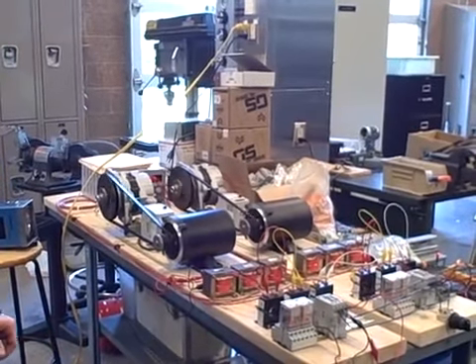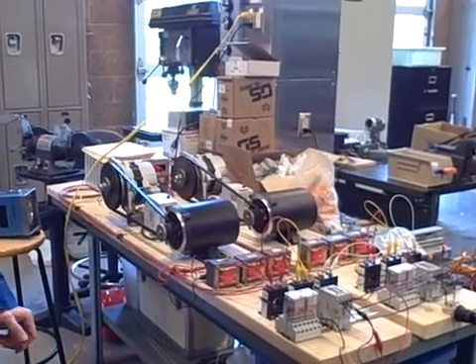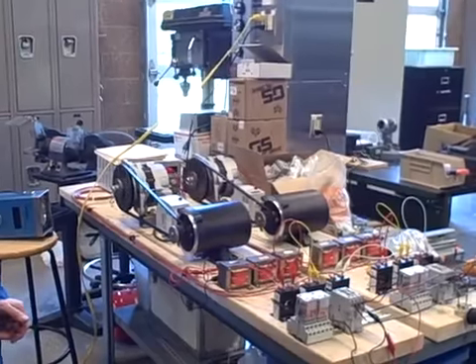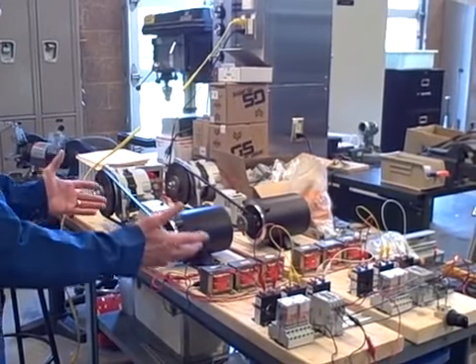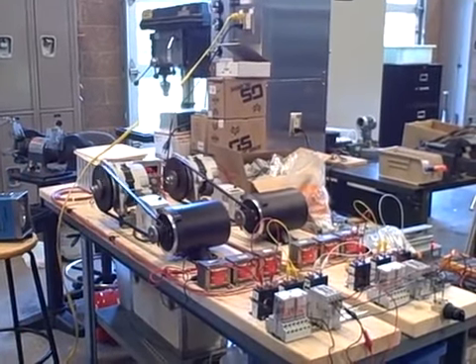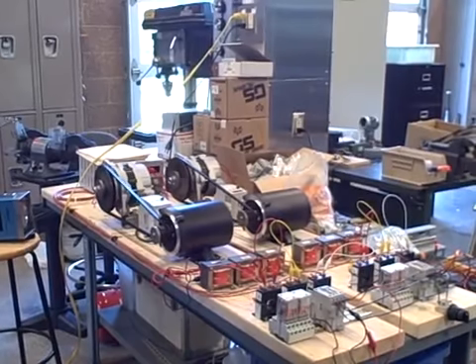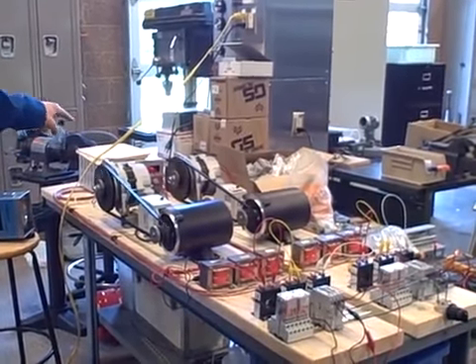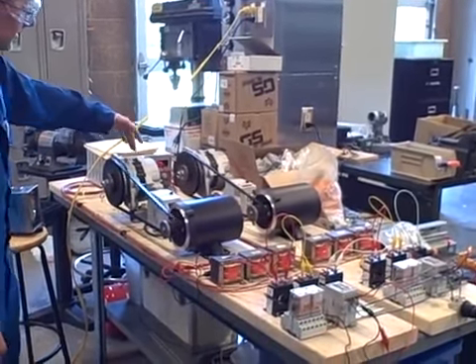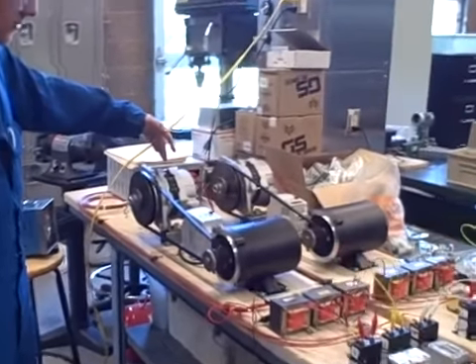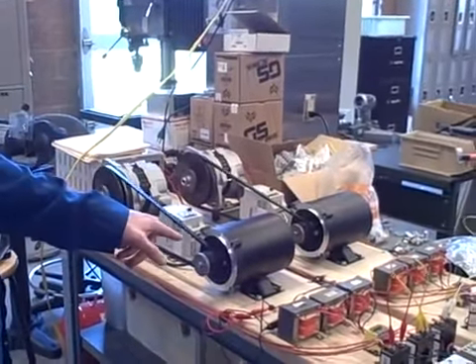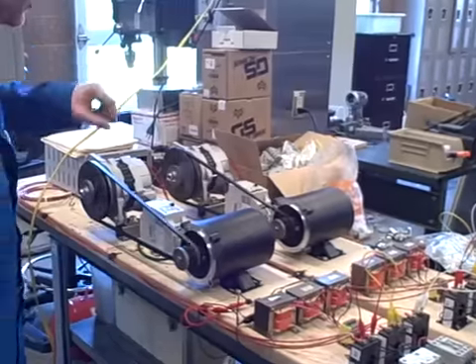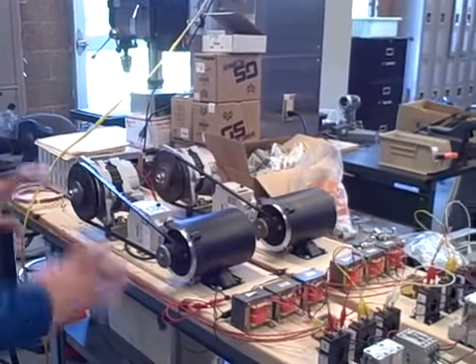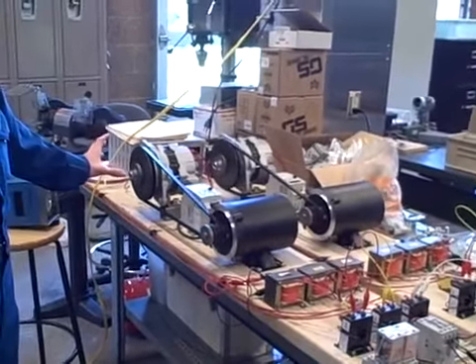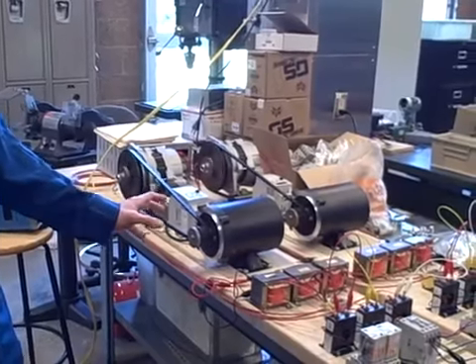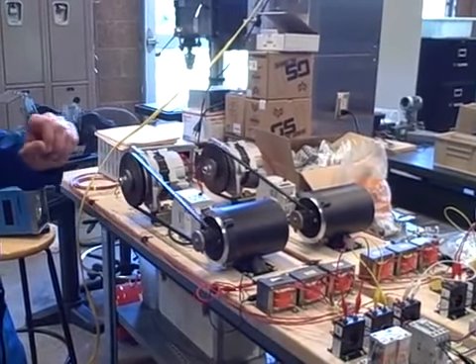So this is going to be a demonstration of synchronizing a pair of AC three-phase generators on a common power grid. What you see here are two generating stations that we have built for a protective relays course here at Bellingham Technical College. Each generator is a three-phase unit. It's actually a Delco Remy alternator for a heavy-duty truck. We're spinning it with a three-phase motor connected to a variable frequency drive so you can change the speed very easily. This is simulating a generator at a power plant being spun by a steam turbine or a water turbine or something of that nature.